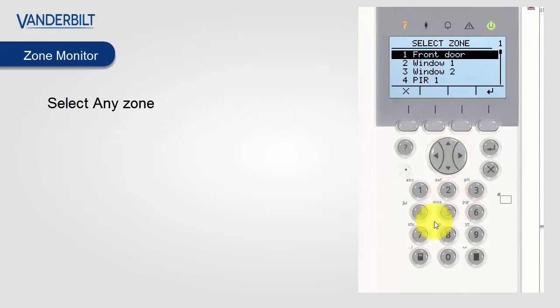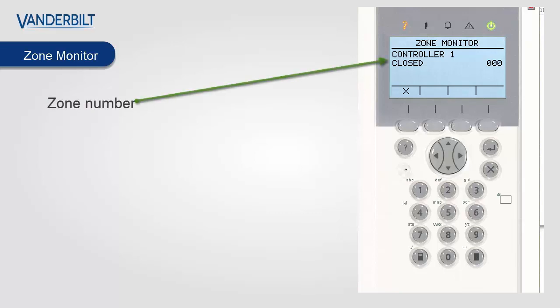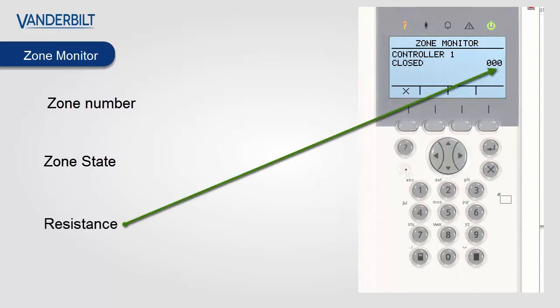In order to use the tool we can select any zone on the system. The zone overview will display the status of the zone and its location. This zone is located on controller 1. If the zone is located on an expander this will also be displayed. We can see that the zone state is closed, and when the zone changes state this will update. We can also see the live resistance of the zone, which can be useful for determining if the wrong end-of-line has been selected.